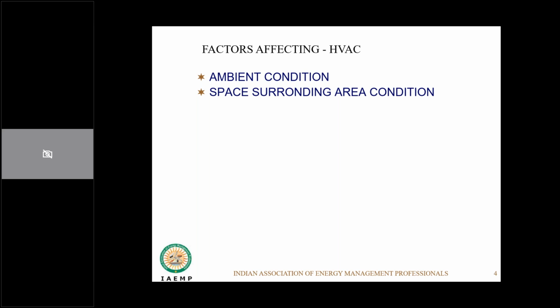Space surrounding the air conditioning. This is again a very important factor. Let's say you have a small air conditioning unit zone. You want to create an air conditioning zone very close to your furnace area. Then you have to take into account the heat that would be coming through that furnace, radiated through that proximity of the furnace area, into your design. Otherwise, you will fail. Normally, when you have a small control room for these furnace areas, you need to take that into account when you are maintaining its controls in a controlled environment. So surrounding areas need to be factored in.